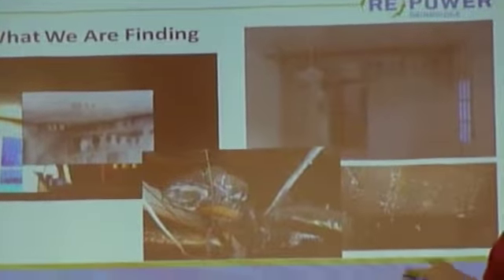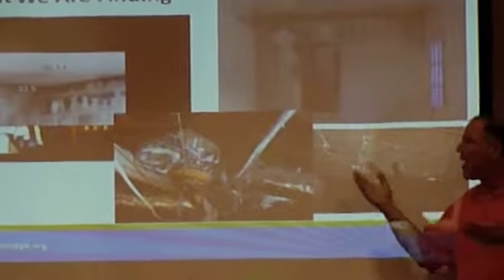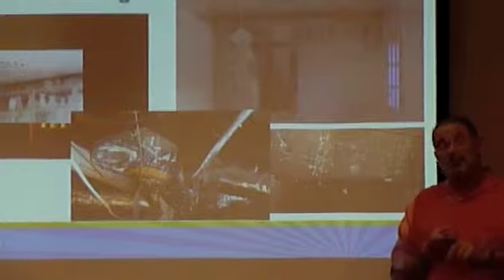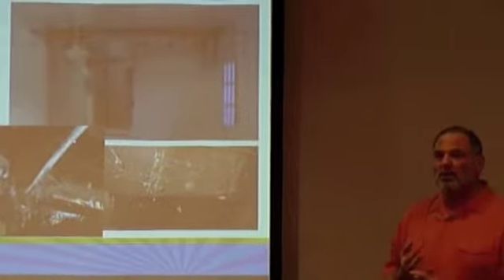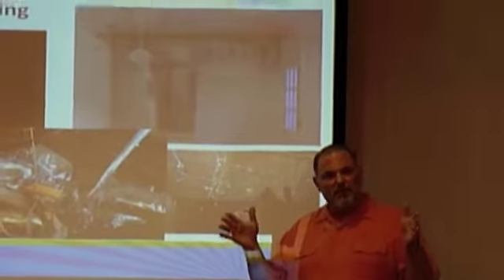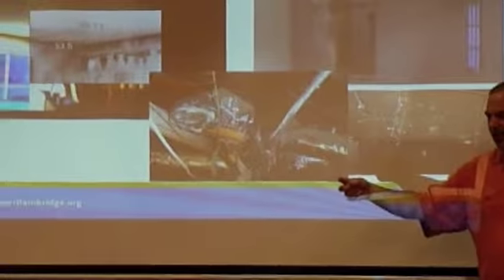And this is common. If I can tell you that it's more common than not, I mean it. We see it all the time. Why do we use flex duct? It's certainly more expensive than hard pipe, but it's easier to install and it's already insulated. We like to see it in small footage. We like to see a piece of hard pipe that runs the entire length of the house to a boot, maybe 2 or 3 feet long, and sealed properly on both ends.